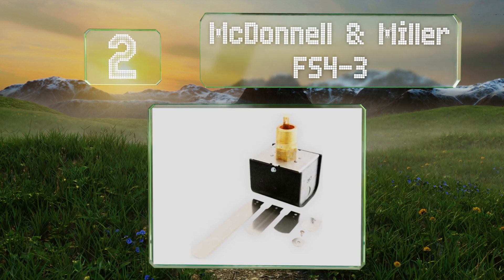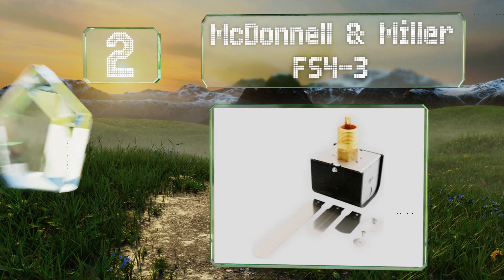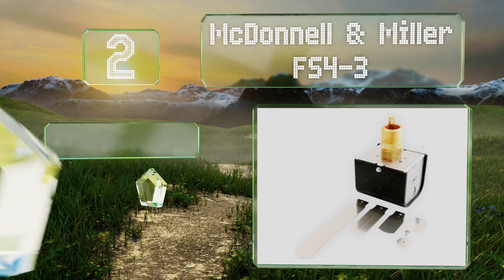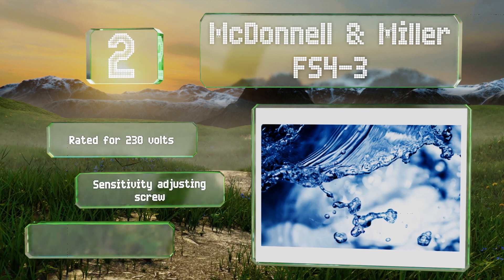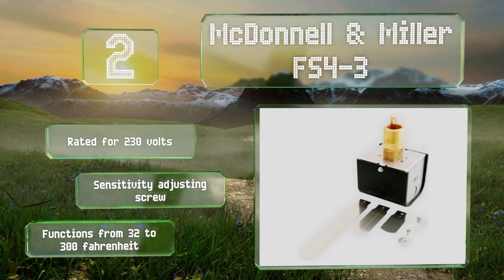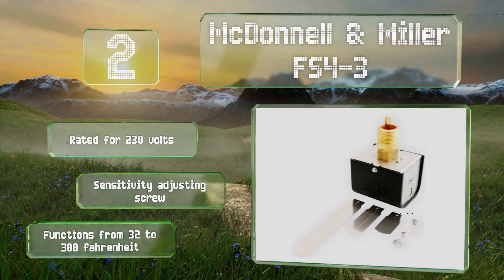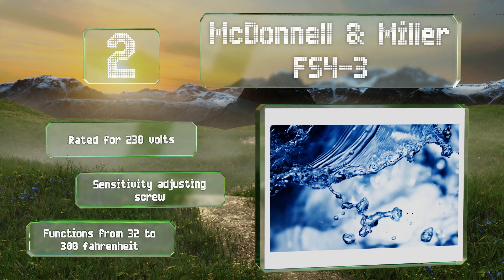At number two, four stainless steel paddles are included with the McDonnell & Miller FS4-3 in sizes from one to six inches, which enables this device to measure flow in as many sizes of pipe. This junction box comes with two knockouts for the installing electrician's convenience. It's rated for 230 volts and includes a sensitivity adjusting screw. It functions in temperatures from 32 to 300 degrees Fahrenheit.